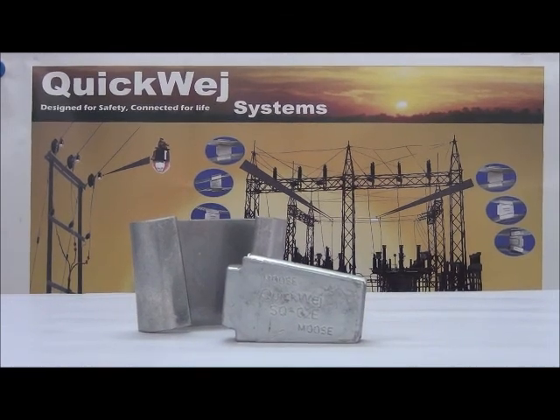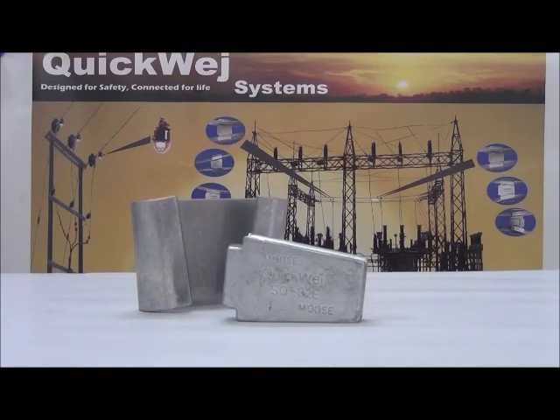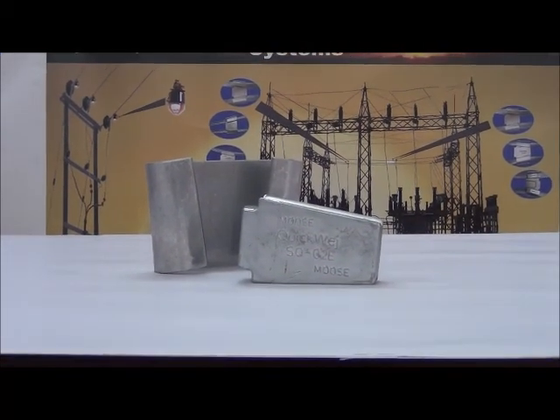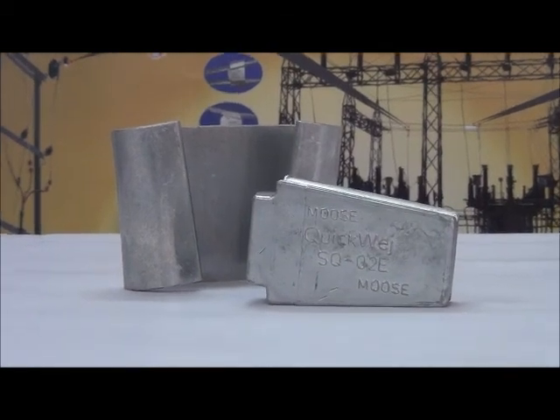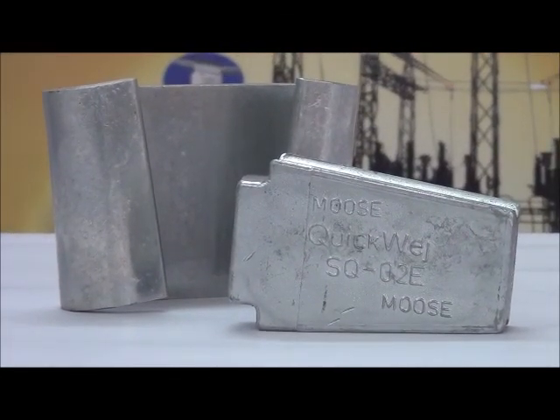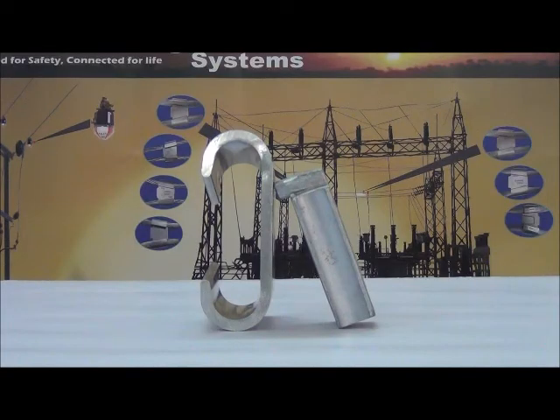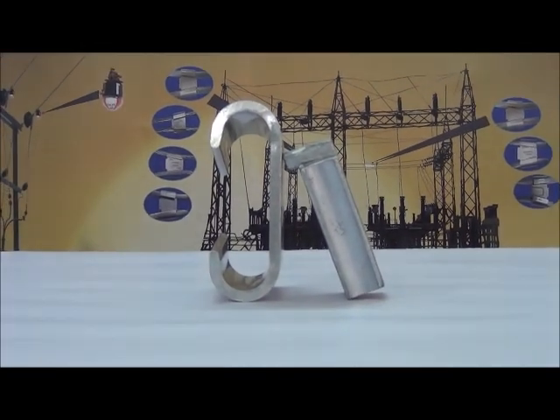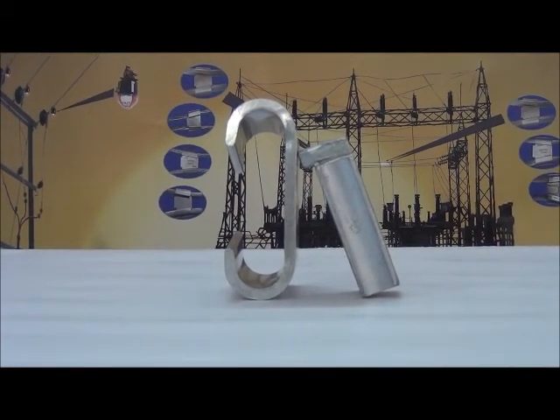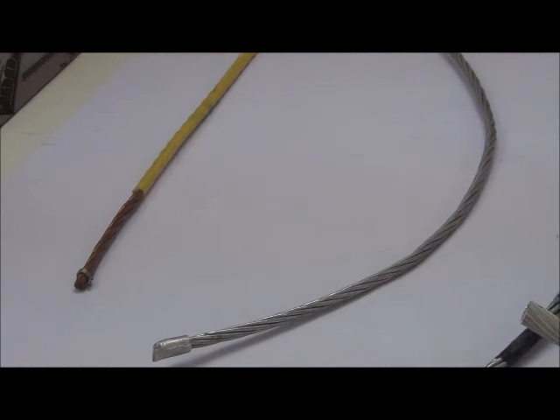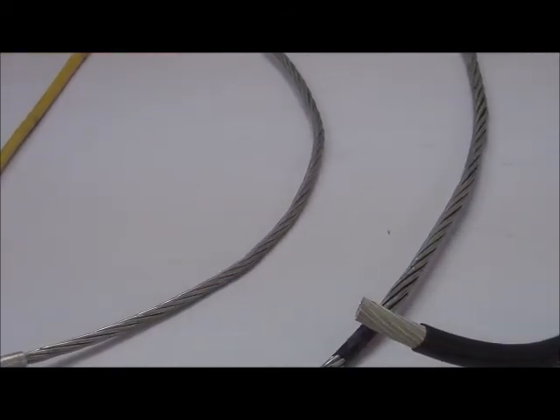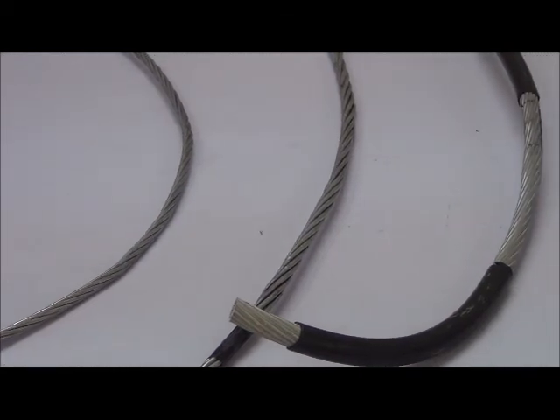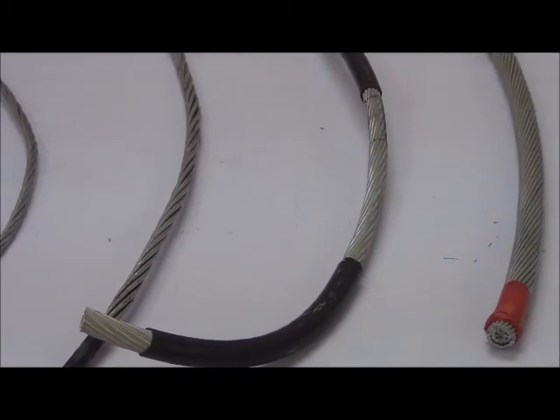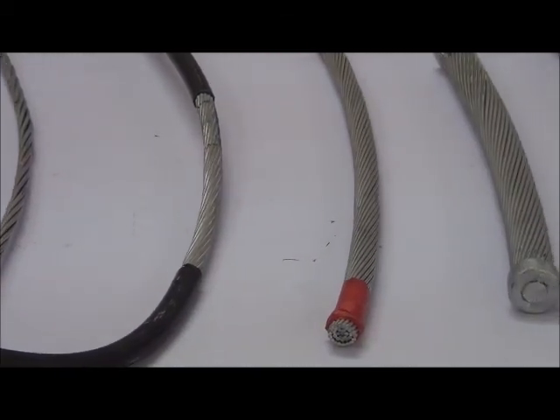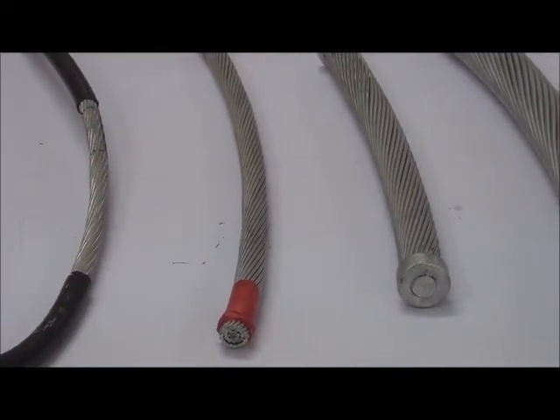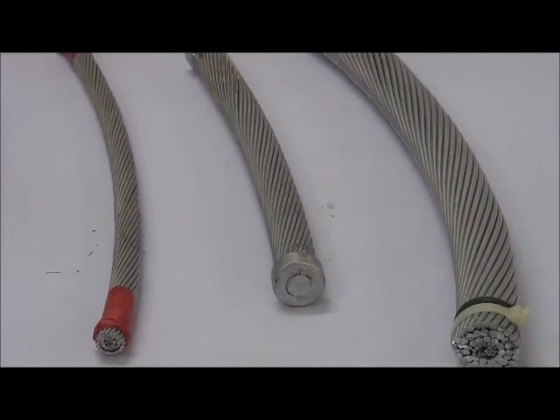Information like conductor sizes and weight of the hammer for installation are mentioned on the connectors. Each connector is specific to the size mentioned on it. This exclusive feature ensures maximum contact between the conductors and the connector and thereby enhances the connector's performance. QuickWej is available for practically all sizes, combinations, and types of conductors, including but not limited to ACSR, AAC, AAAC, SACs, copper, and solid conductors. Connectors are available for conductors with cross-sectional area as small as 10 square millimeters up to as large as 1000 square millimeters.